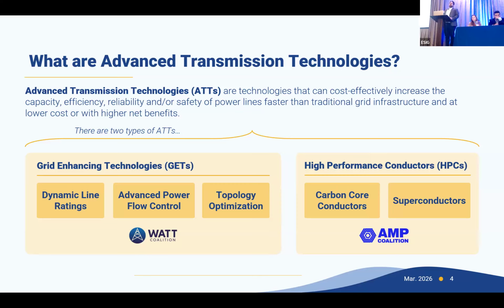For the WATT Coalition, there are three technologies we focus on, ones that dynamically alter the capacity of the grid in some way: dynamic line ratings, advanced power flow control, and topology optimization. These are both hardware and software. Dynamic line rating uses real-time weather and ambient data to adjust line ratings. Advanced power flow control pushes or pulls power to redirect it onto underutilized circuits or away from overutilized ones. Topology optimization we describe as the waze of the grid, looking at grid reconfigurations through an automated process.